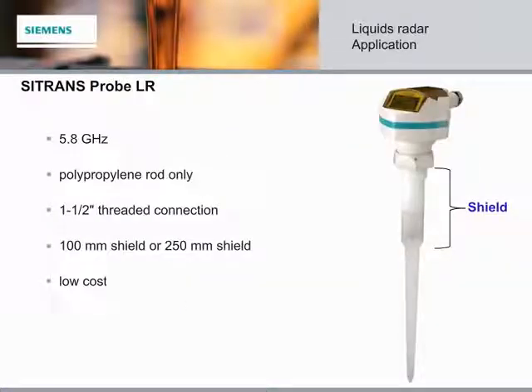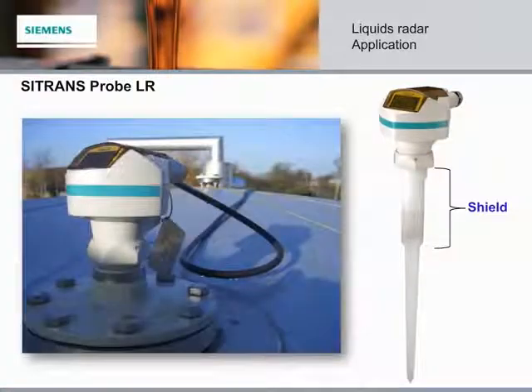First up, meet the SITRANS Probe LR. The Probe LR is a two-wire, 6 GHz pulse radar level transmitter for continuous monitoring of liquids and slurries in storage vessels with nominal pressure and temperature and up to a range of 20 meters. It is ideal for applications with chemical vapors, temperature gradients, vacuum, or pressure, including tank farms, chemical storage, digesters, and those with long-range conditions.